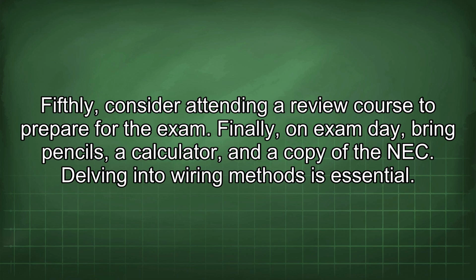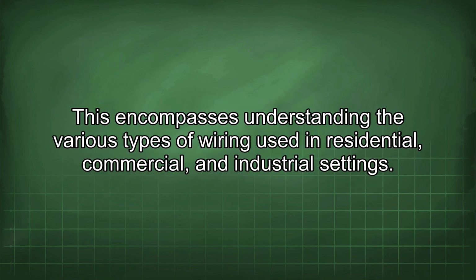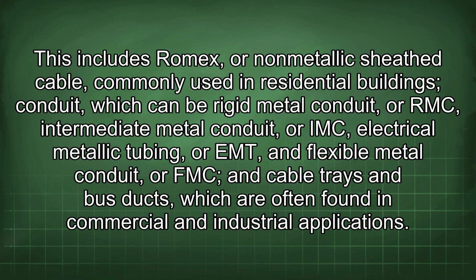Delving into wiring methods is essential. This encompasses understanding the various types of wiring used in residential, commercial, and industrial settings. This includes Romex, or non-metallic sheath cable, commonly used in residential buildings, conduit, which can be rigid metal conduit, or RMC, intermediate metal conduit, or IMC, electrical metallic tubing, or EMT, and flexible metal conduit, or FMC, and cable trays and bus ducts, which are often found in commercial and industrial applications.